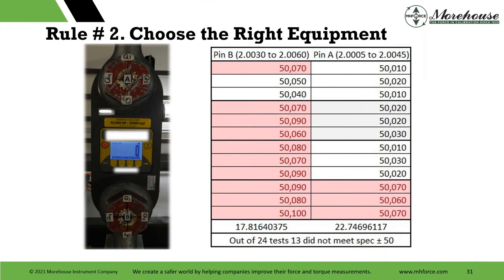Choose the right equipment. Here's one I wasn't sure whether to add, but I really did — this is commercial weighing with a tension link. The way it's gauged and designed, they use these with cast-in pins, and if we rotate those pins around, we get different results. The reason this got us into trouble initially is a customer sends us an instrument like this, and we mark one of the pins with a sharpie or paint pen that says 'top' with an arrow and 'bottom' with an arrow, so when the customer uses it, they can put those pins in exactly the same way they were calibrated.